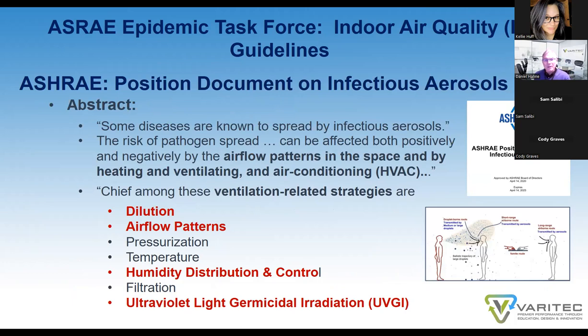The ASHRAE position document on infectious aerosols goes on to state that some diseases are known to spread by infectious aerosols, and the risk of pathogen spread can be affected both positively and negatively by the airflow patterns in a space and by heating and ventilating and air conditioning systems. So how air is delivered into a space can impact the rate of infection. It goes on to state that there are ventilation-related strategies to reduce the risk of infection. Not only is there dilution, there are also airflow patterns, pressurization, humidity distribution and control, ultraviolet germicidal irradiation. These are topics I'll be covering in today's presentation. That's the reason why they're highlighted in red.